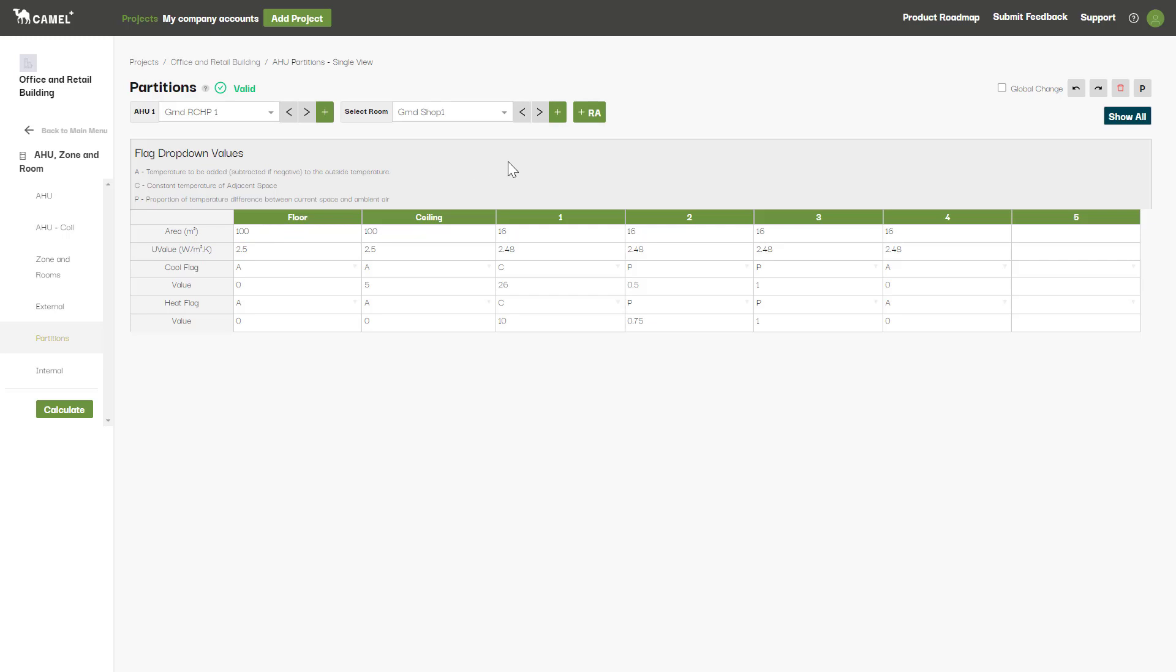The C flag is probably the easiest to understand. This allows you to just enter a constant temperature for the adjacent space. For example, for this partition one here, the adjacent room has been specified to be 26 degrees at all times for the cooling load calculation and a constant 10 degrees for the heating load calculation.